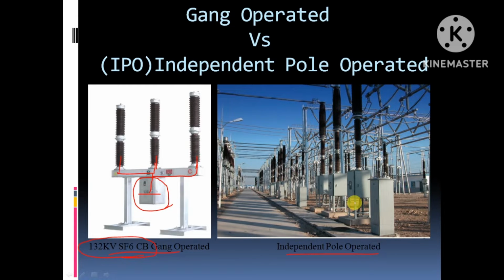In the independent pole operation, for each phase you will find an independent spring charging mechanism. A separate mechanism will be there. So if you consider R, Y, B, each phase has a separate mechanism box, and the pole operation is independent. That's why it is called independent pole operated. And here, this is called the top pad and this is called the middle pad. The contact separation during the breaker operation will take place between the middle pad and the top pad.